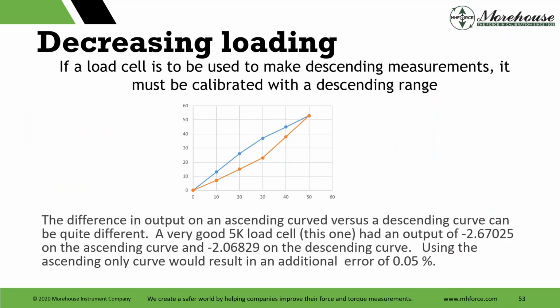A difference on a good 5K load cell like we're seeing, using the ascending only curve would add an additional error of about 0.05%. And that's basically saying, hey, my ascending point is this, and my descending point is this. The difference between this curve and that curve is 0.05%.